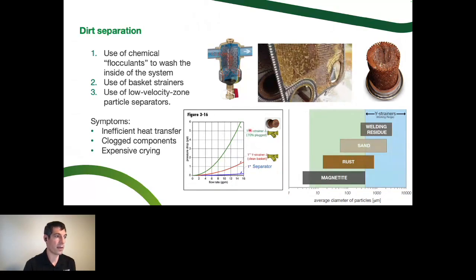Even as you turn up the flow rate through these devices, you can see that the pressure drop across the separator is very different from a plugged Y strainer that's going to add a ton of pressure drop across, in this example, 12 GPM, 70% plugged. We're adding like a 4 psi drop across that device. That's going to take you out of your design considerations for what pump size you needed in that case. We don't want that. We don't want to start to choke the boiler for the flow rate that it's looking for, as an example.